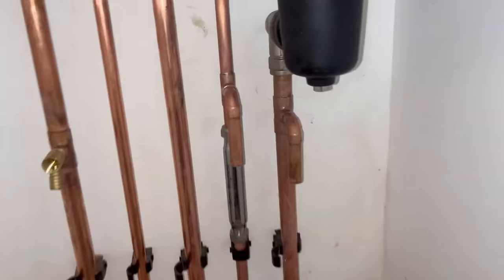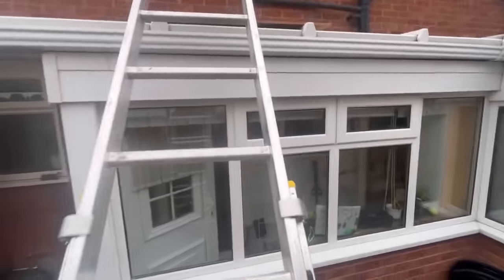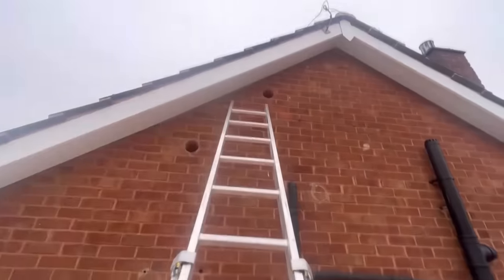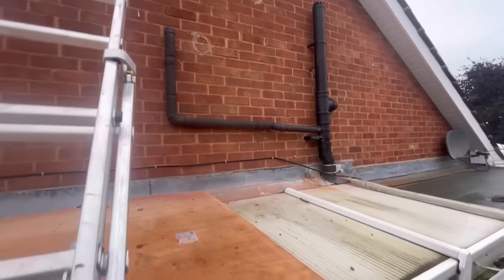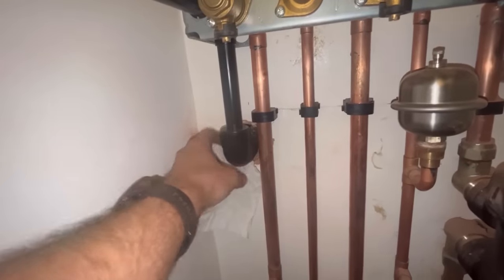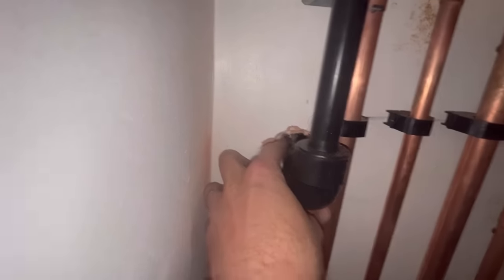Mistake corrected — yes, we've got it ready to go. This is how we've done the condensate — a bit wobbly. We put a board down just in case when we core drilled anything fell on there. Elbowed it down and lagged it. There was no lagging on that before. Filters in, condensate graded 32mm. Got a big massive hole there from the core drill — never mind, we'll sort that all out.